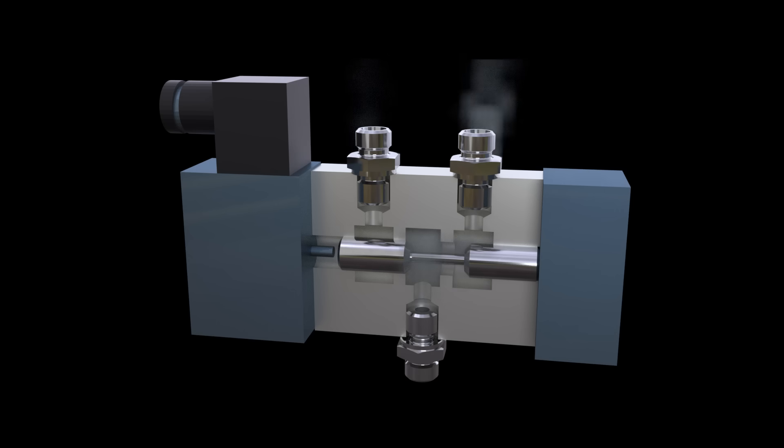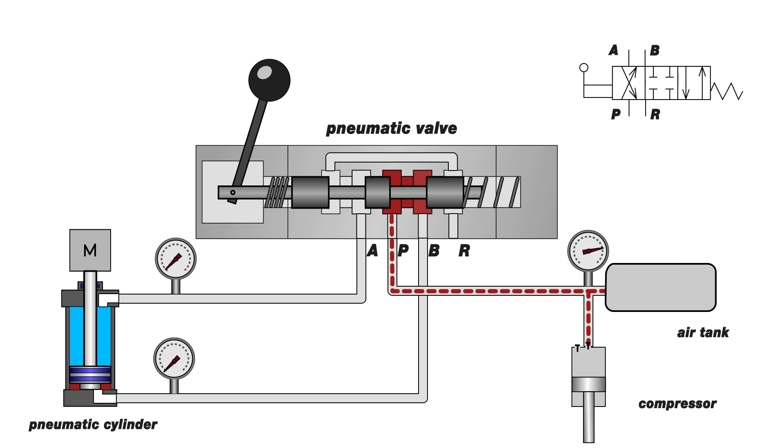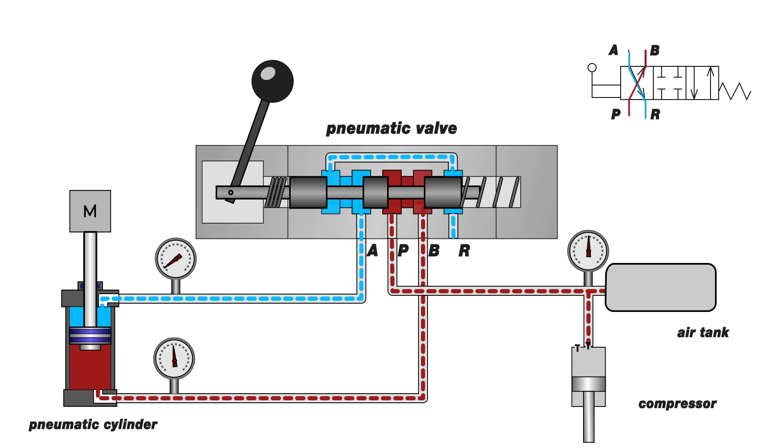Let's consider the operation of the pneumatic system as a whole. Air moves from the compressor to the valve, which is locked in the neutral position. When switching the valve, compressed air will move from the compressor to the piston cavity, and the rod cavity will connect to the atmosphere. The rod will extend.